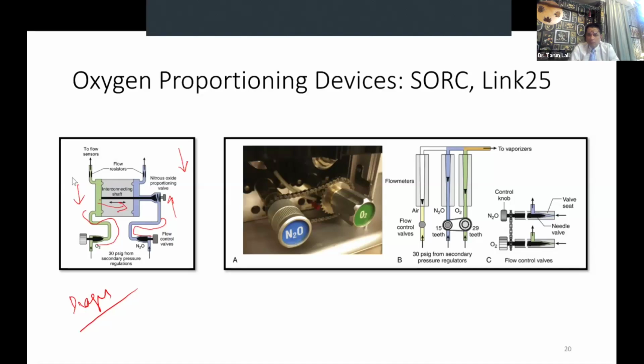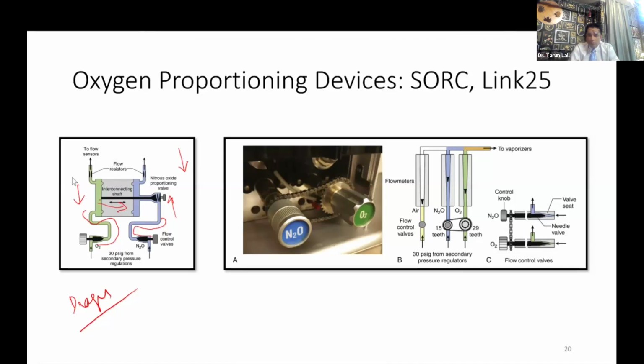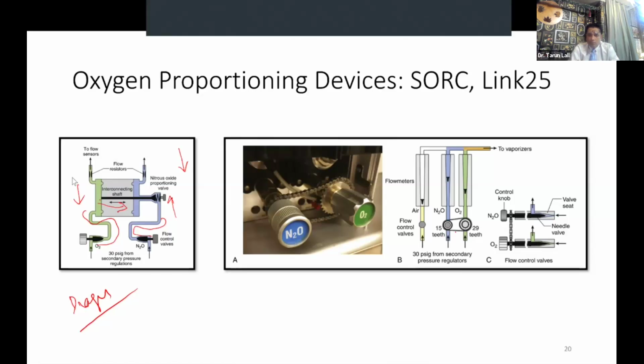The more mechanical type of device which we see in most of our machines these days is the Link-25. Link-25 works on the principle of differential cogs in the oxygen and nitrous assemblies. On the nitrous oxide side, we have 15 teeth, and on the oxygen side, we have 29 teeth. This means that each turn of the oxygen flow control knob will result in two turns of the nitrous oxide knob. So the ratio delivered is 1:2, or 33% oxygen. But it is called Link-25, which means that it will give at least 25% oxygen. So with this arrangement, the ratio given is 1:2, or 33% oxygen.